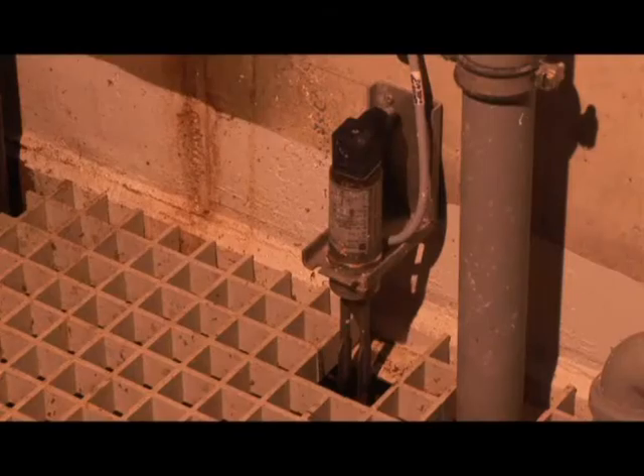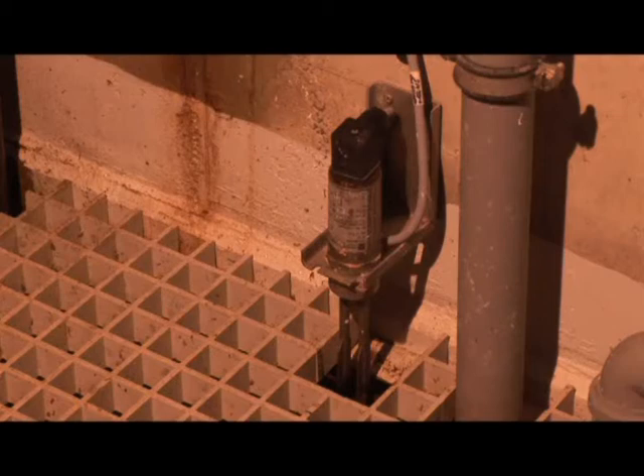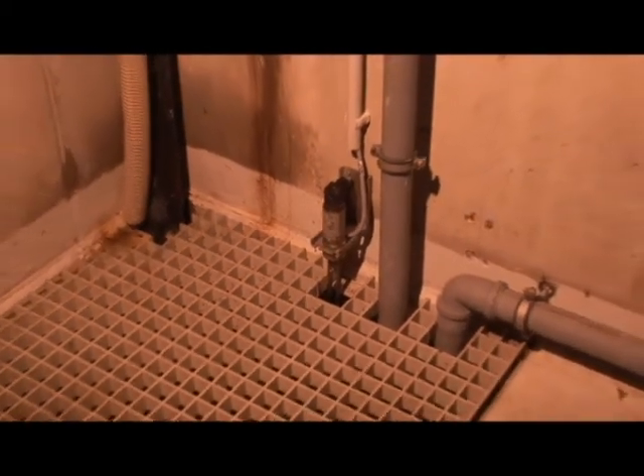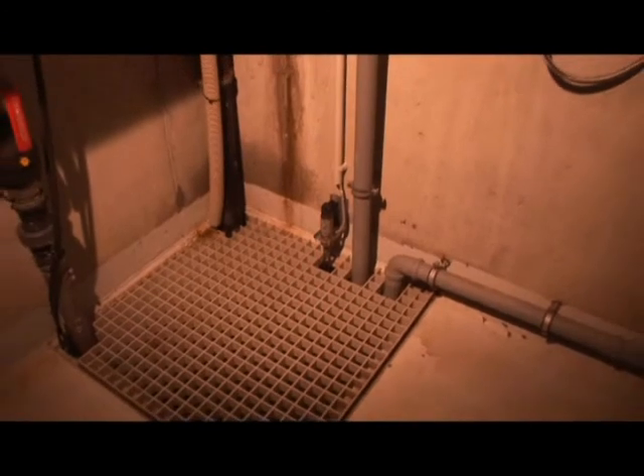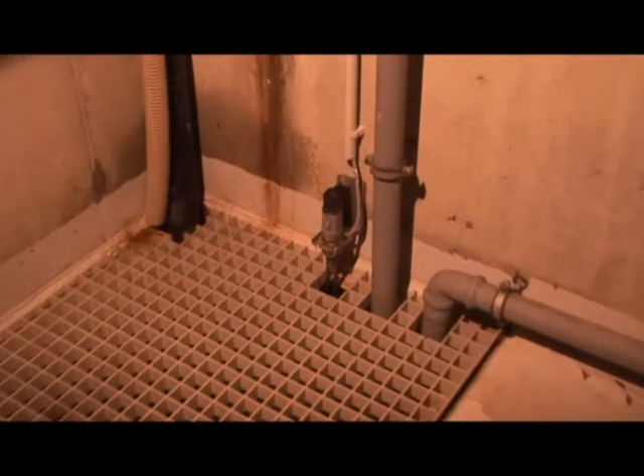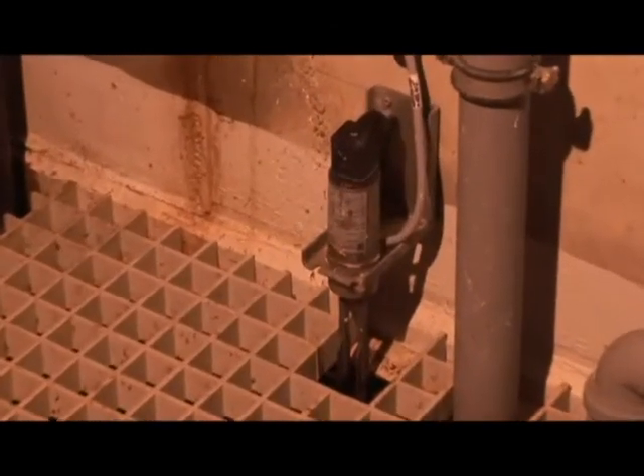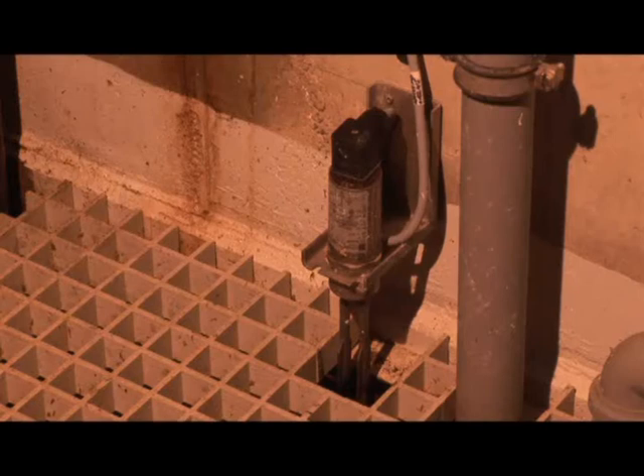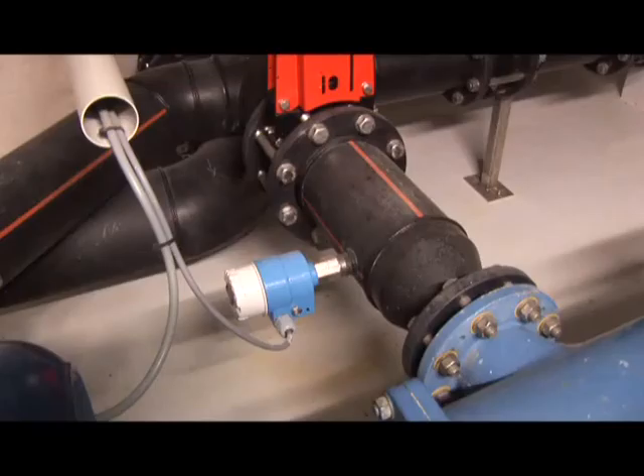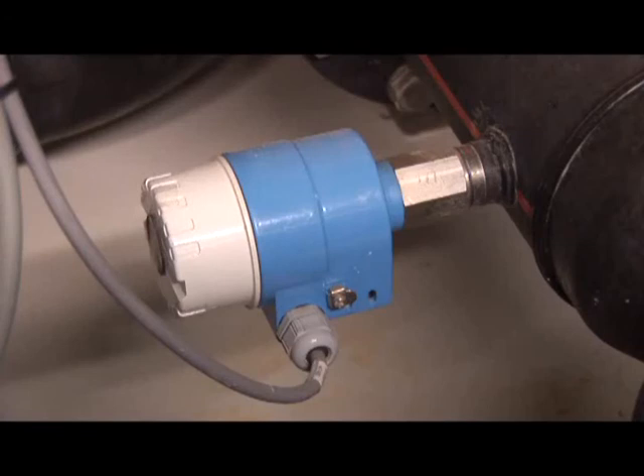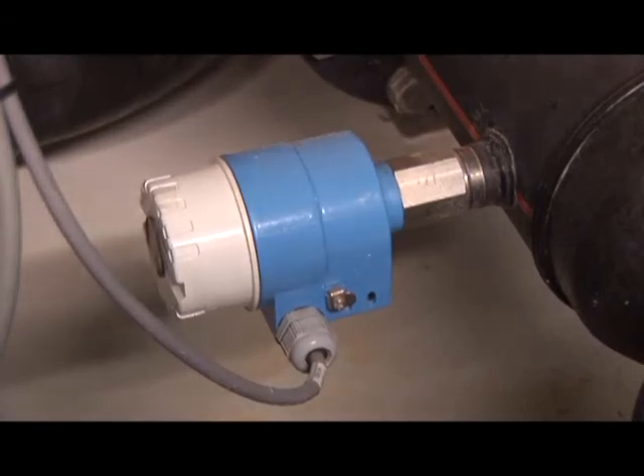filtration process. This Liquiphant FTL 260 monitors the deepest portion of the wastewater treatment facility. If the Liquiphant provides a notification, this means that somewhere a large volume of liquid has leaked out. The facility is completely surrounded by a thick basin in which this liquid can be retained. If the Liquiphant provides a notification, all facilities can be brought to or locked into a secure state. Also, in membrane filtration, a pump protection switch is deployed in order to prevent pump damage by dry running.